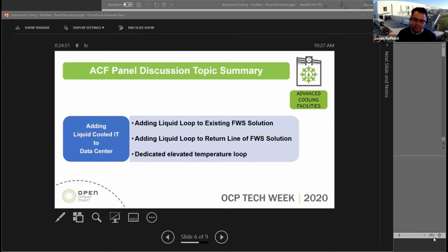So with taps, and they're 4-inch taps on them, and with them in both cray galleries, we can actually provide even added redundancy, resiliency to the liquid cooled load by coming off of each branch, the one on the south side and one on the north side. So we've also worked that into our design, and this also has the benefit if we need to subdivide our suites a little bit. We can also use those taps either for liquid cooling or additional fan wall units to provide the same level of resiliency for our clients. Great, excellent, thank you.